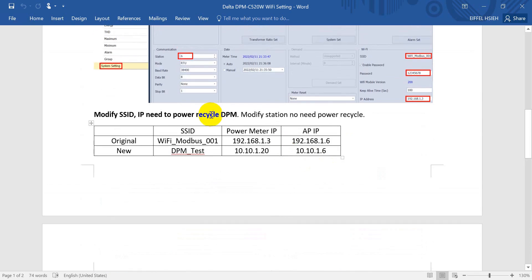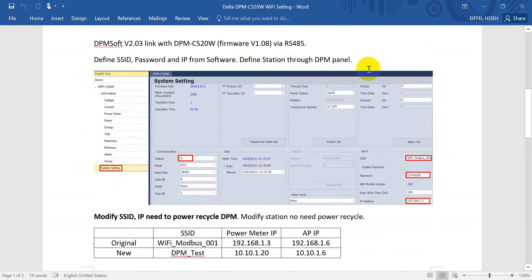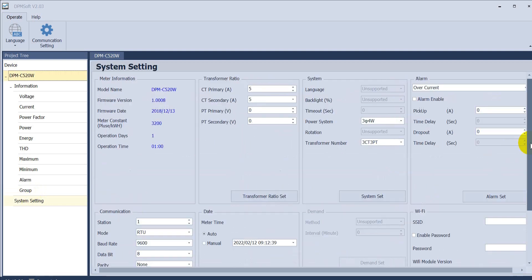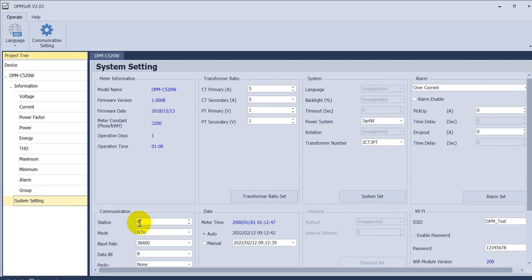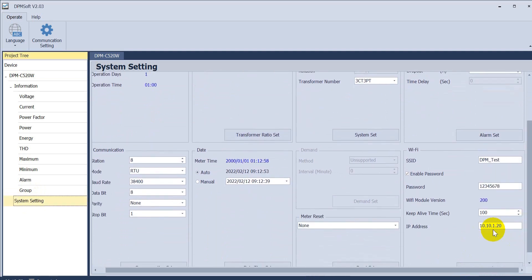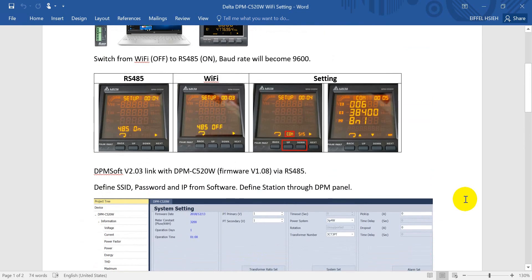The last thing I want to mention is modifying the station address. The station address should be modified from the DPM panel. We will change it from 6 to 8. Use IP 10.10.1.20 with station 8, then connect. Click system settings and you will see it has already switched to 8 with the correct SSID and IP. That's all for today's topic. Thank you.